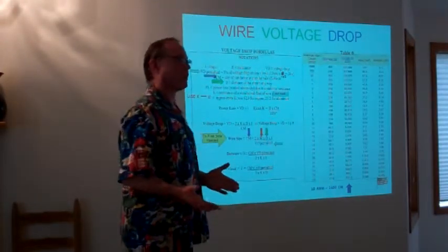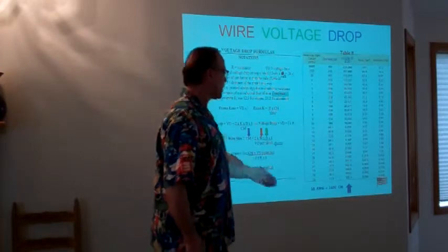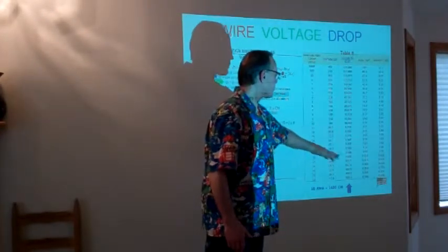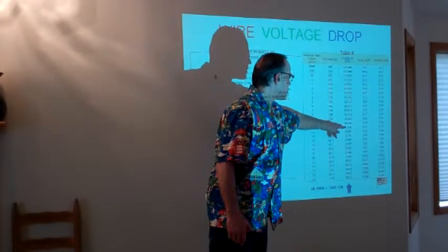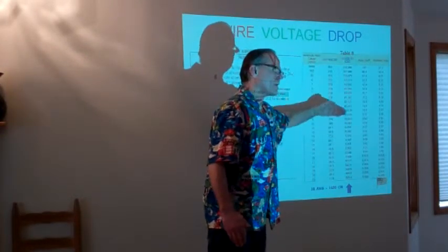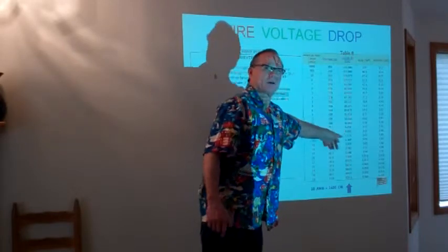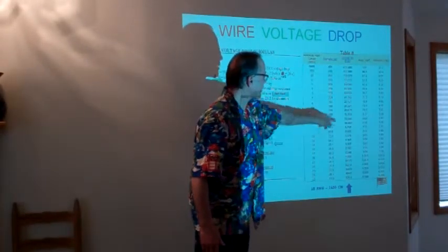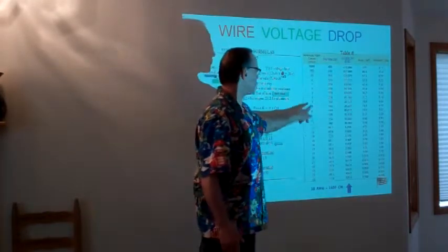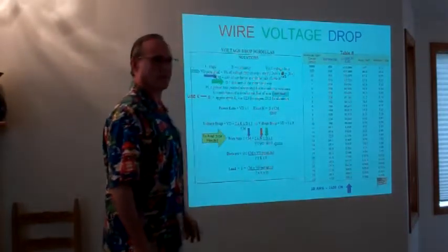So the way this chart works and the way that we work with that formula is we find that number of circular mills, we come to our chart, and we find the number that's going to be closest to it above that level. Or if you're right at it, of course that would be what you would use. And this is the wire number we want to use. We're not going to use circular mills, we're using circular mills to determine our wire size.